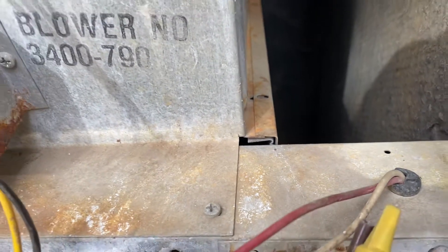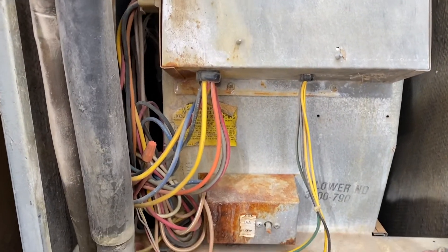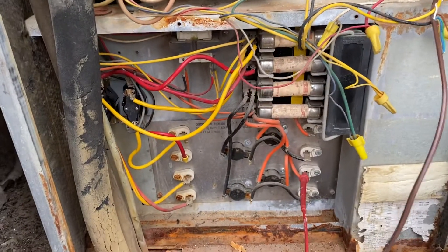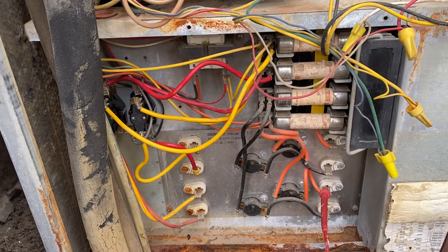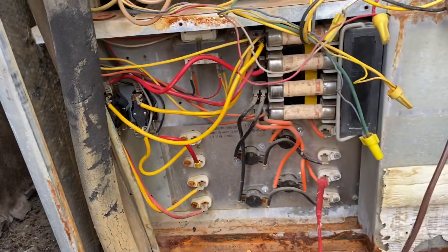They do turn on — it's kind of hard to see, but right from that crack I can see it. I saw another gentleman open up the blower in his video so you can see the heating elements better; I'm trying to avoid doing that. What's happening is it's tripping my 60-amp circuit breaker, and I thought replacing the sequencers would fix that — it doesn't.